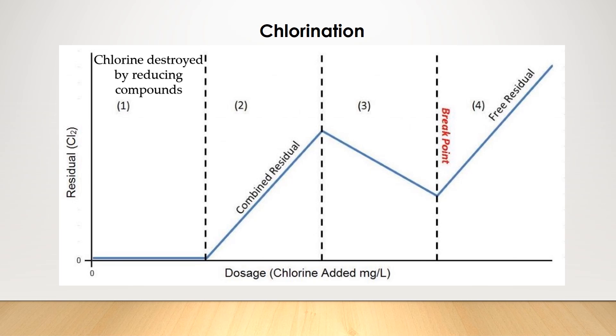As you keep pumping more chlorine into the water, you move into Stage 2. Here you have the formation of what's called chlororganics and chloramines — chemicals formed when chlorine reacts with things like organics and ammonia in the water. The blue line is now trending upwards, meaning we have chlorine residual in the water, but it's in the combined state. Combined chlorine residual is chlorine that has attached itself to something else like ammonia, and it is not as effective as free chlorine residual, which is what you want.